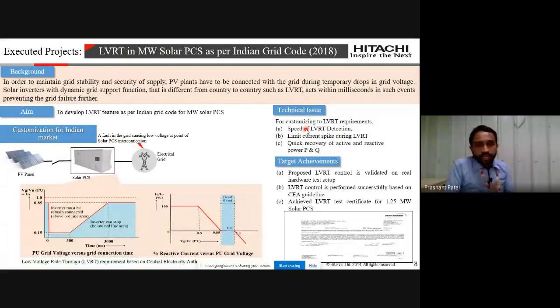According to LVRT, whenever there's a dip in the grid due to a fault, the voltage goes down, but for a certain duration you should not disconnect your solar inverter from the grid. During that time you have to provide reactive power to the grid. The duration and the amount of reactive power are decided by the Indian grid code, and all of this has to happen within a stipulated time period — that's the real challenging task.